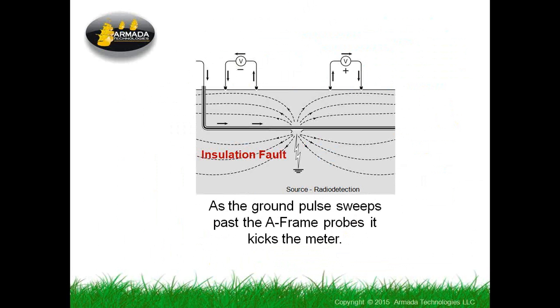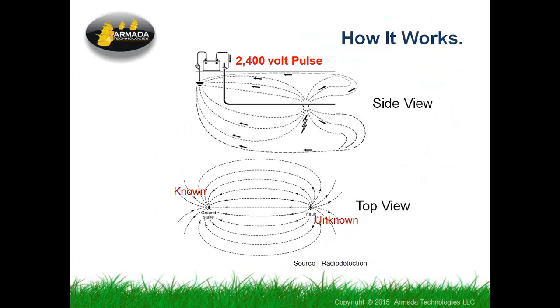This is the whole concept behind the use of the ground fault locator, which is why the A-frame is kind of a big unwieldy thing. It's got two probes that are about 3 feet apart with a meter that mounts in the middle. The way this works, in the case of GFL 3000, you can select between a couple of different voltage levels, but the lowest is, believe it or not, 2400 volts. Because it's a fairly small damage point potentially on the cable, a small nick in the insulation or something, we use a pretty high voltage, and it creates this nice sweeping path through the earth that goes back to the ground rod where the A-frame pulsar unit is located.